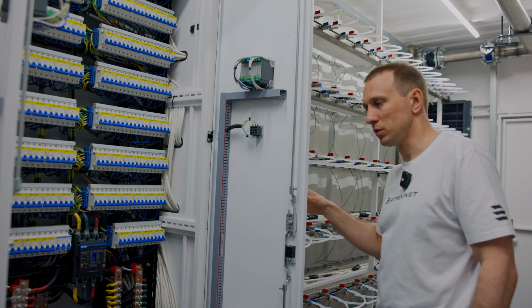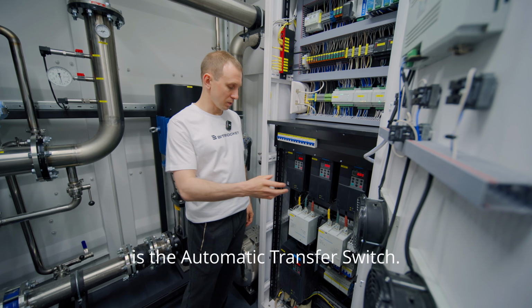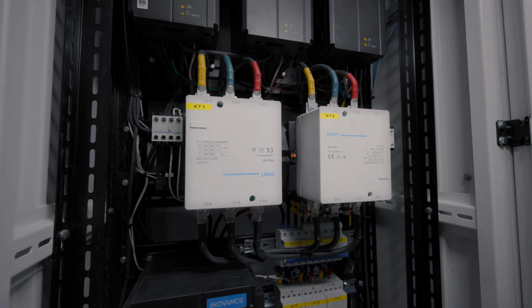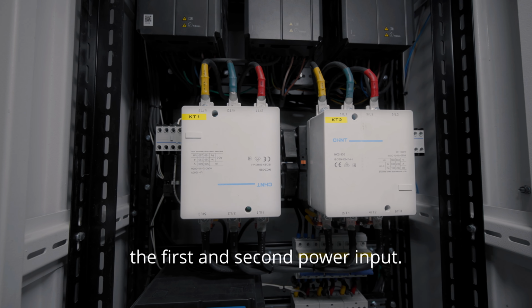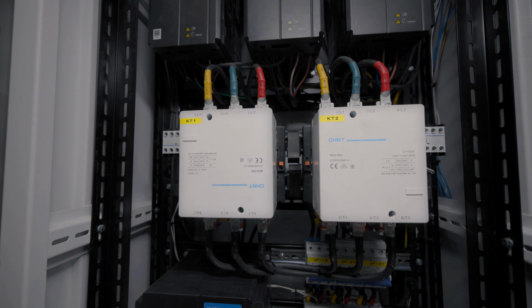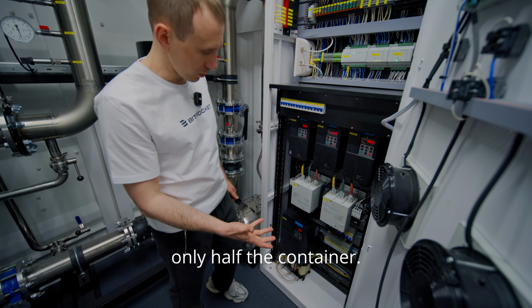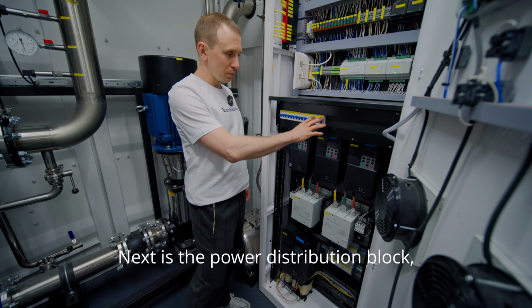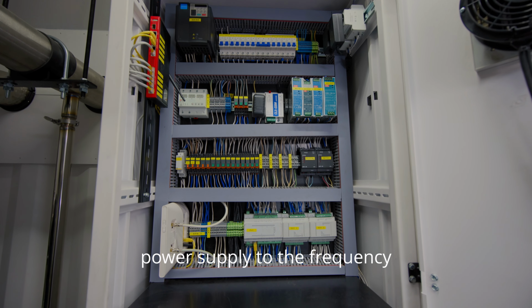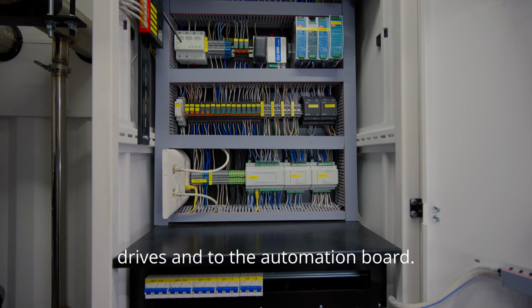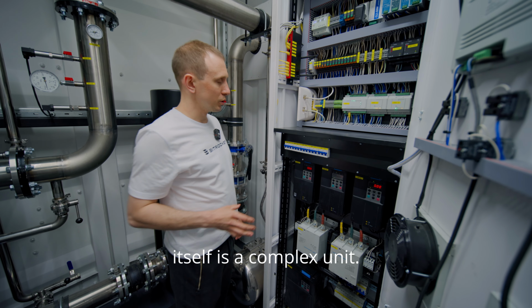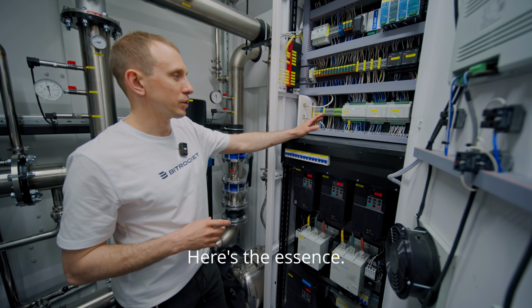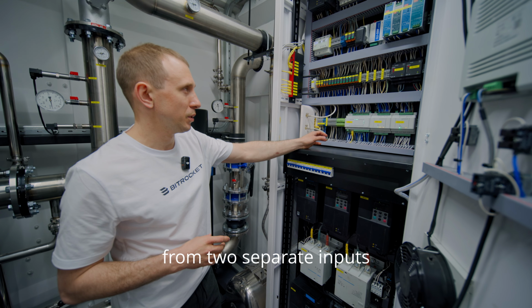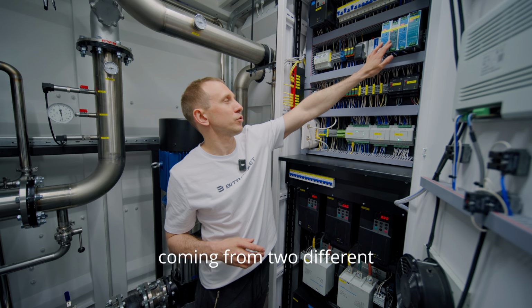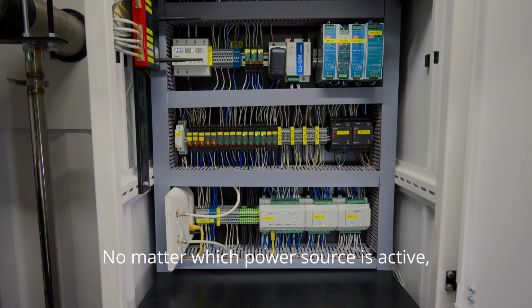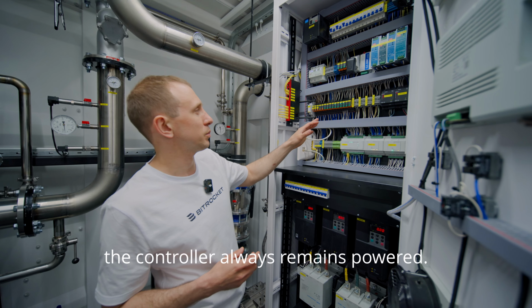We can move on. The automation cabinet's main component is the automatic transfer switch. Its primary function is to switch between the first and second power input. This allows you to power only half the container. Next is the power distribution block, where we distribute the power supply to the frequency drives and to the automation board. The automation board itself is a complex unit. Here's the essence. The controller is powered independently from 2 separate inputs coming from 2 different cabinets. No matter which power source is active, the controller always remains powered.